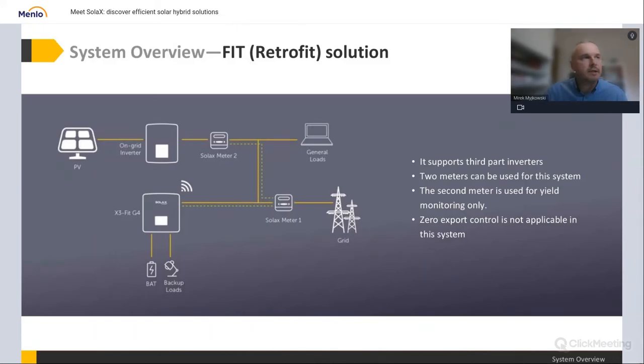Another slide is about what happens when there is another source of power in the house. Here we've marked this as an X3-Fit, but it can be a hybrid with its own PV installation. There can be 2, 3, 4 PV installations in the house with different inverters. It doesn't matter, as long as our SolaX meter 1 detects any extra power trying to go to the grid. This power will be used by our Fit or hybrid inverter and redirected into the battery. And the Fit or hybrid inverter will supply the house with battery power when there's no PV power anymore, or not enough of it. That's how it works—automatically.